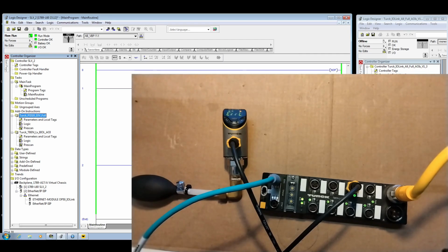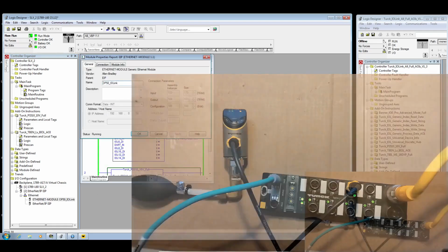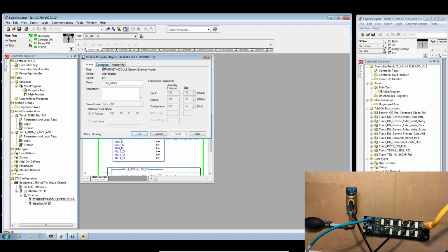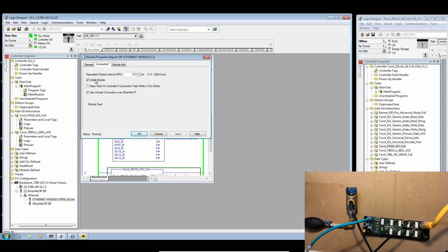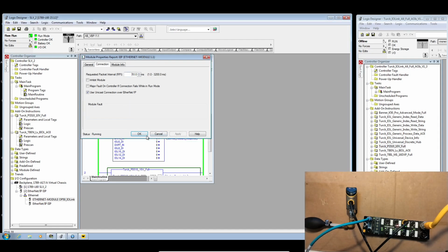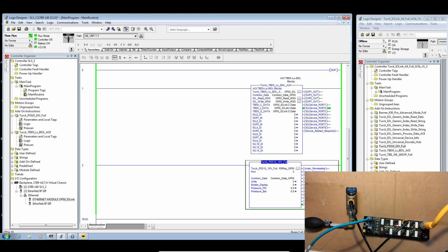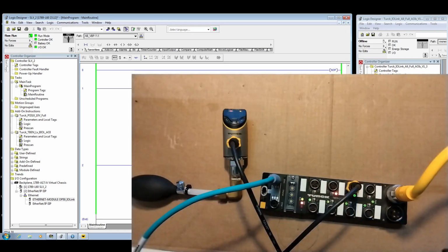So it's actually expecting it to be on port 3, but there's no red lights. This is probably the biggest gotcha right now: the C data is set to expect the IO link device. However, the C data has not been implemented yet. The C data only gets implemented on connection of a device. So whether you disconnect and reconnect the Ethernet, or if you restart the PLC or something like that. So what I'm going to do is inhibit and uninhibit the module, which is going to allow a reconnection to occur, and it will then send the C data. Let's zoom in. There we go.